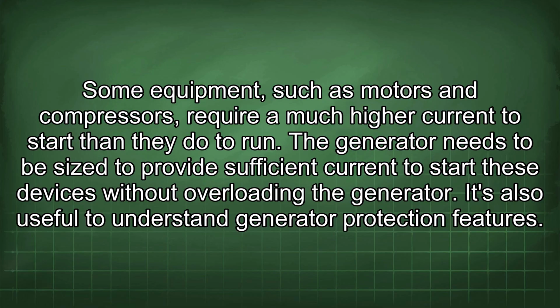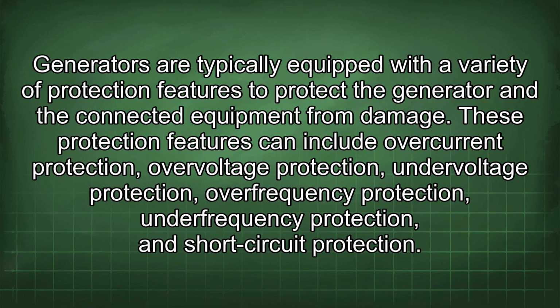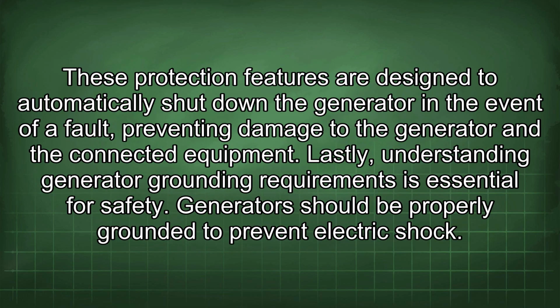It's also useful to understand generator protection features. Generators are typically equipped with a variety of protection features to protect the generator and the connected equipment from damage. These protection features can include overcurrent protection, overvoltage protection, undervoltage protection, overfrequency protection, underfrequency protection, and short-circuit protection. These protection features are designed to automatically shut down the generator in the event of a fault, preventing damage to the generator and the connected equipment.